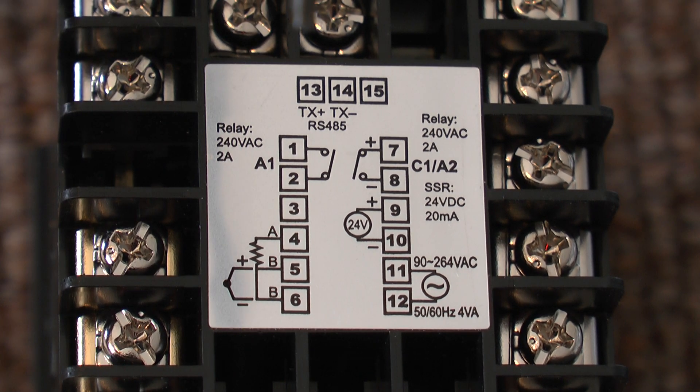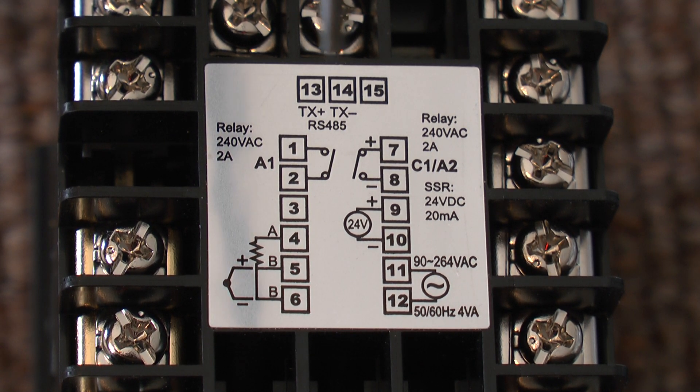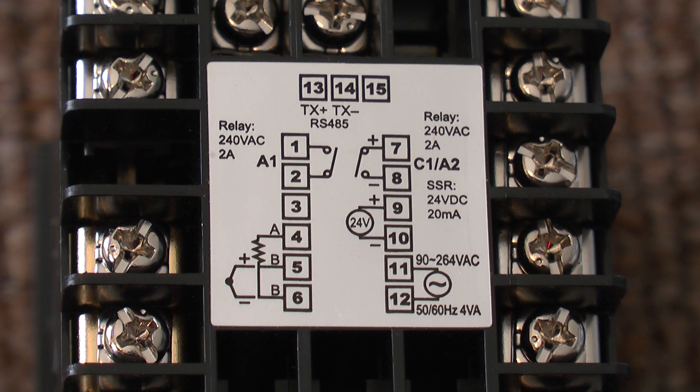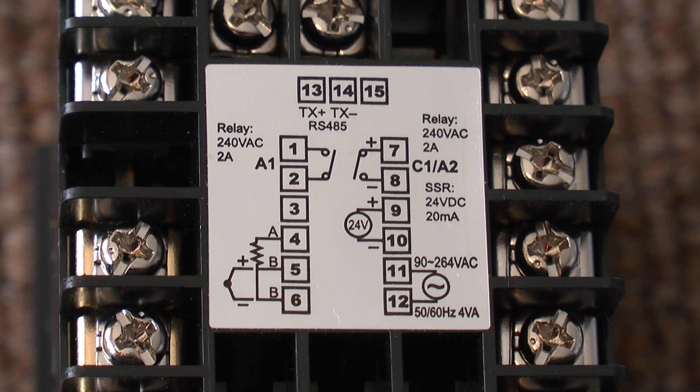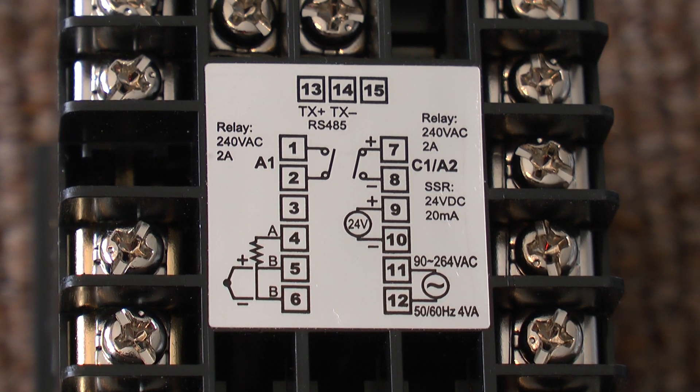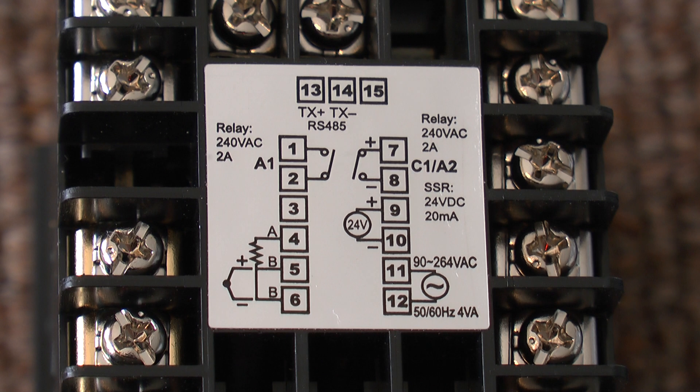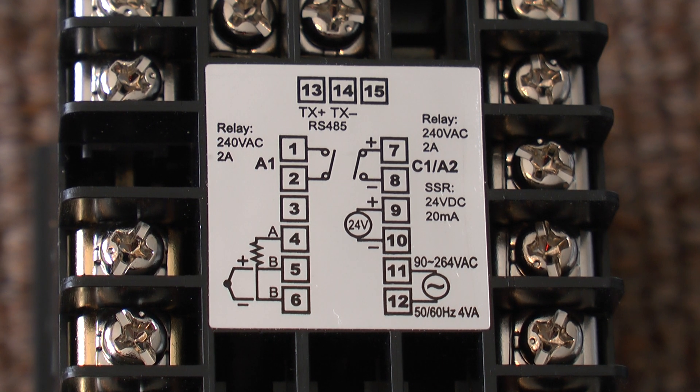If you have chosen an RS485 option, then terminals 13 and 14 are the terminals for that connection. The 24 volt DC output available on terminal 9 and 10 can only drive 2-wire transmitter devices because it is an extremely low power signal.